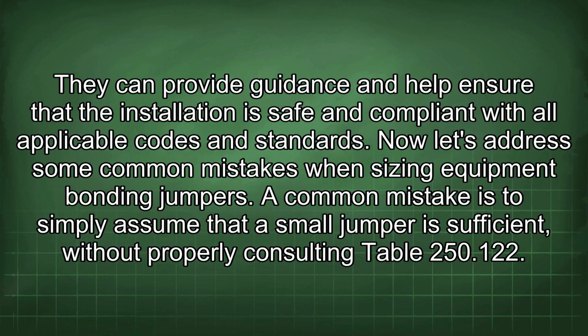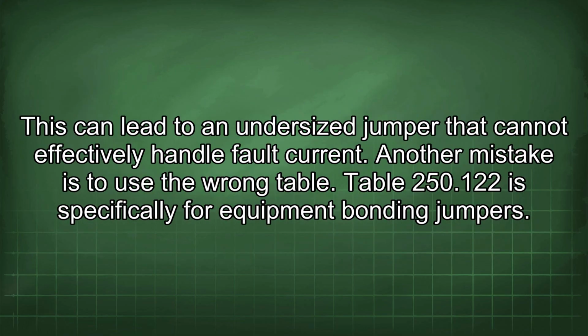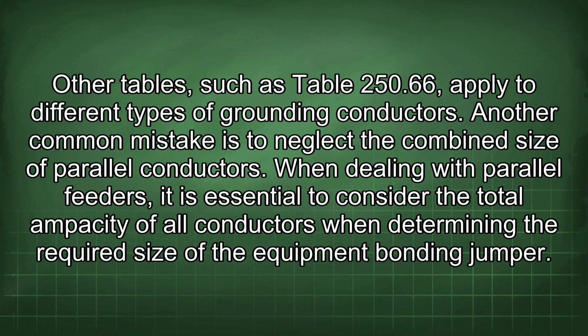codes and standards. Now let's address some common mistakes when sizing equipment bonding jumpers. A common mistake is to simply assume that a small jumper is sufficient, without properly consulting Table 250.122. This can lead to an undersized jumper that cannot effectively handle fault current. Another mistake is to use the wrong table. Table 250.122 is specifically for equipment bonding jumpers. Other tables, such as Table 250.66, apply to different types of grounding conductors.